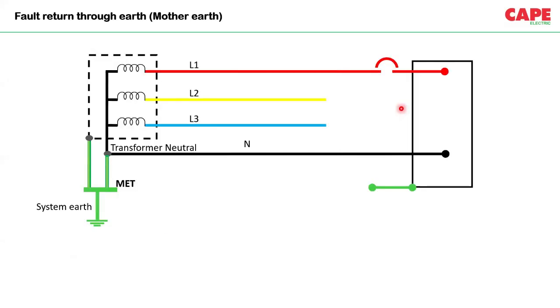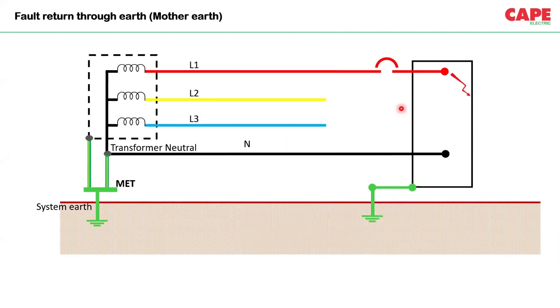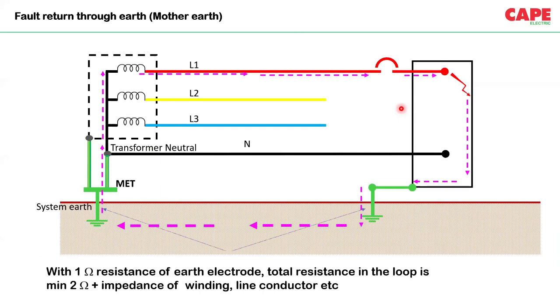So now coming back to our subject, automatic disconnection. One of the networks which we use is a TT, where the fault current is going to flow through the earth electrode. And you have to be clear that this earth electrode has a certain resistance. And in this particular loop, there are two resistances added by two of these earth electrodes. Let's say, for example, in an ideal situation, each of these earth electrodes is 1 ohm. Now, with these two earth electrodes, we are actually adding 2 ohm in this particular loop.